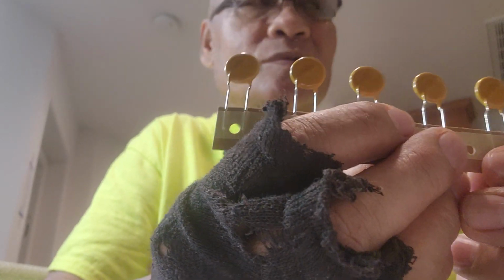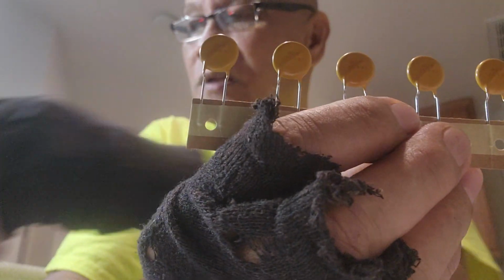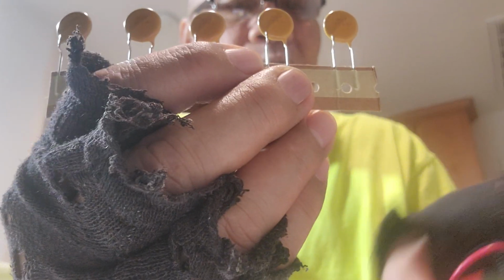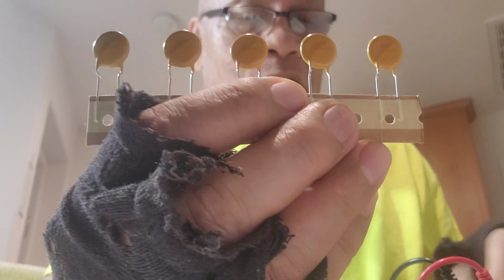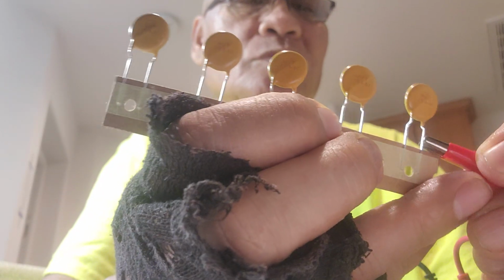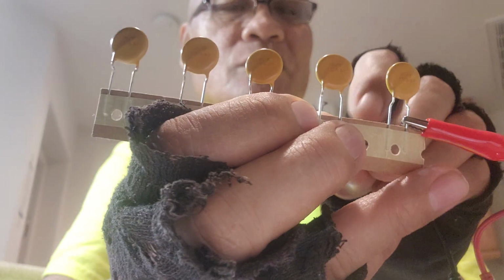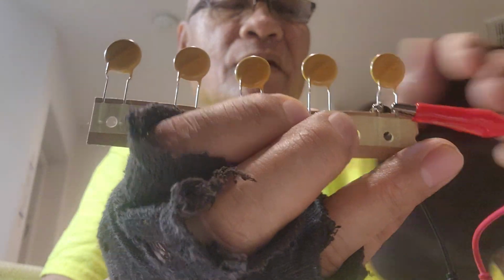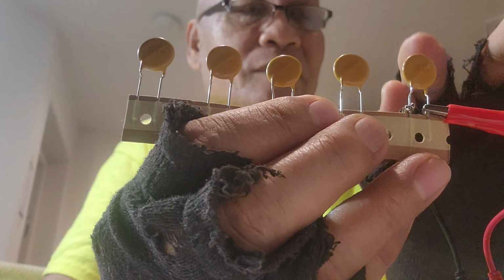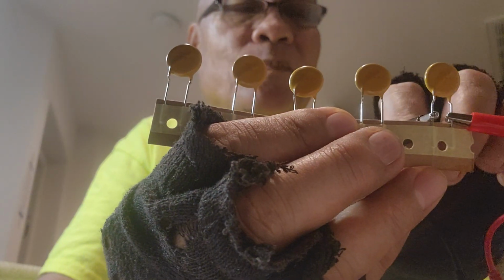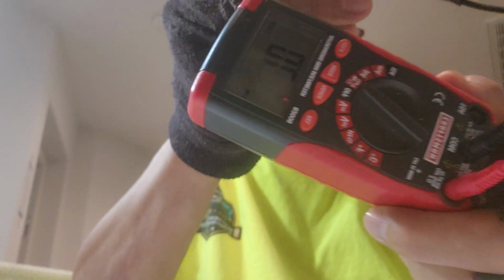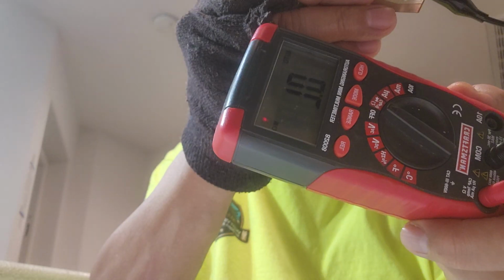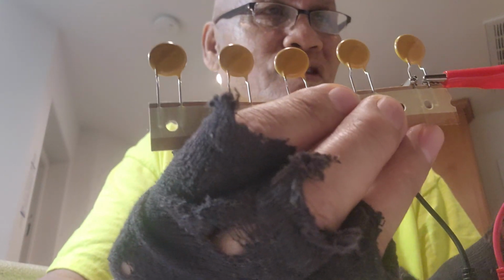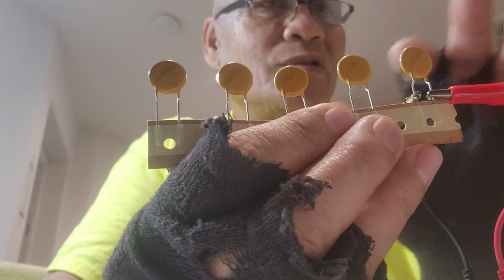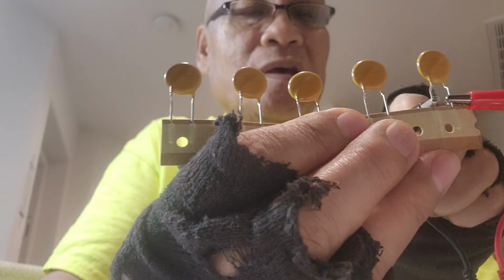The proper way to know if this surge protector is good or bad is to measure. You will get your multitester and set it on the ohm range. Then try to measure the resistance between the two terminals. For a voltage surge protector to be in good condition, the reading should be OL. It should be an open circuit. Meaning to say, if the surge protector is in good condition, its resistance is an open circuit.